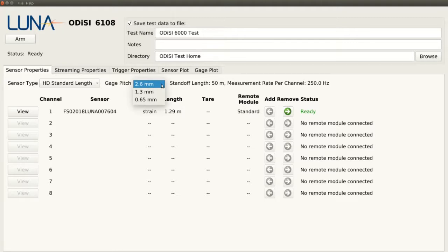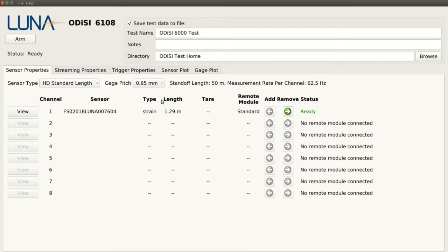The 0.65mm mode, for example, has four times the measurement density of the 2.6mm mode, but the trade-off is that these measurements are taken at a quarter of the rate of the 2.6mm mode. Depending on the type of experiment, one mode may perform better than another.